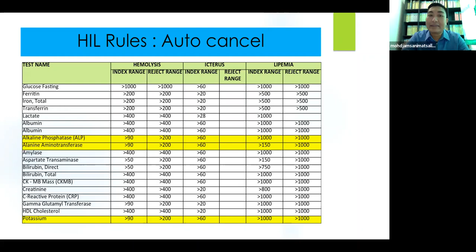So it's important for us to gather all the information from the package insert to know every single test in the lab that is available, with the specific interference for each of the tests. So we have to have some tables to tabulate all the interferences and what is the cutoff at which we decide certain tests won't be reported. So this is how it's transformed into the computer's language or program. It is transformed into interference checking for each of the analytes. And these are examples of our tests where we cancel and we have an automated comment for each of the tests to make sure that every result is safe to be released.